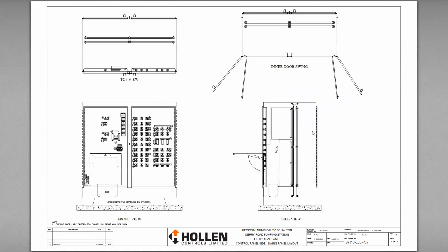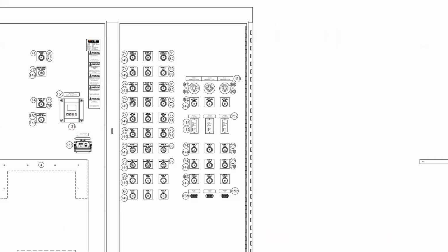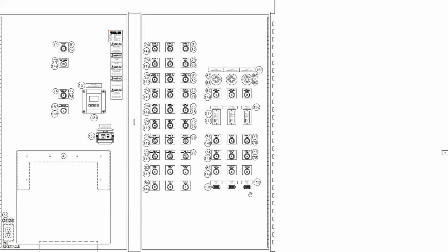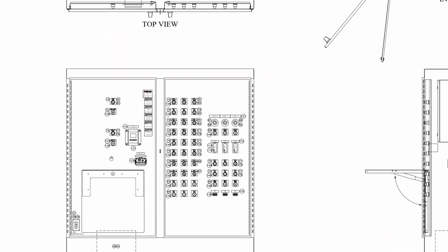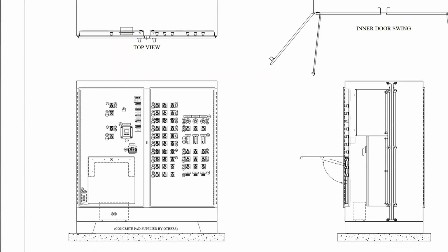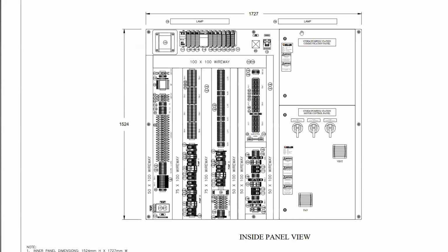It had additional jumper panels inside of it. And then on the control side, we had an inner swing door, and we had the hand-off-auto and all the lighting control for the pumps, plus their automated backup system. So they ran on VFDs, but they also had starter backups in the event that their VFDs failed, and the PLC was behind that panel. When the second one swung out, there was the PLC panel, and here was the storm panel pumping control. The backup control was in here. There's all your different terminal blocks. That layout you could see in the last drawing.